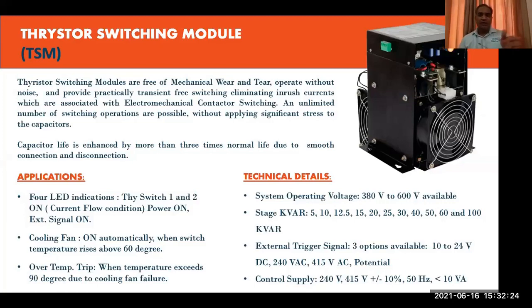So we have our own thyristor switching module from a minimum of 5 kVAR up to 100 kVAR. We have a good design; the fans are available from a minimum of 25 kVAR module up to 100 kVAR for good heat transferability. It is 10 to 24 DC operable, with external trigger, and control supply is 240.